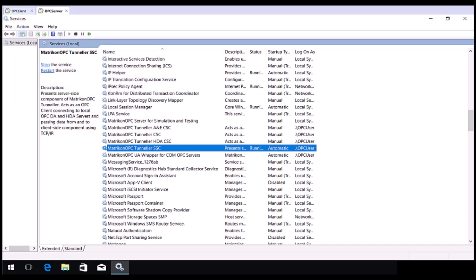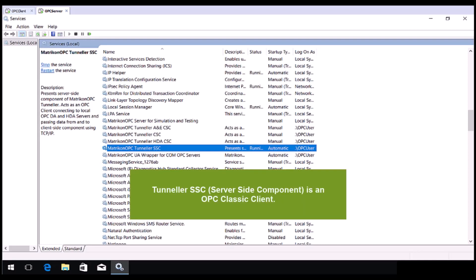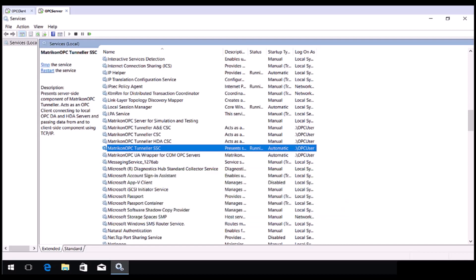This is a good time to tell you that some OPC servers require the OPC client to be running as a specific user in order to access them. The MatrikonOPC Tunneller SSC is actually the OPC client that will be connecting to your OPC server. You can set this service to logon as a specific user if required.